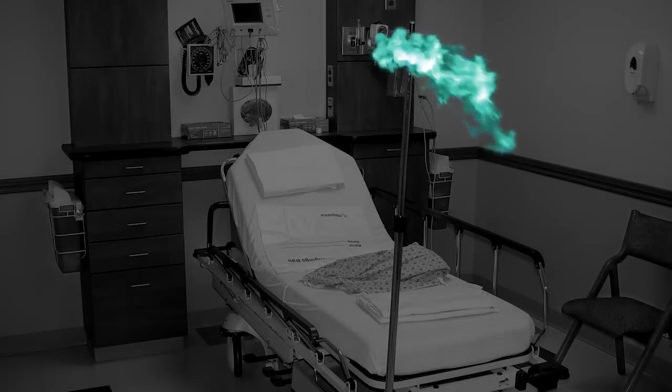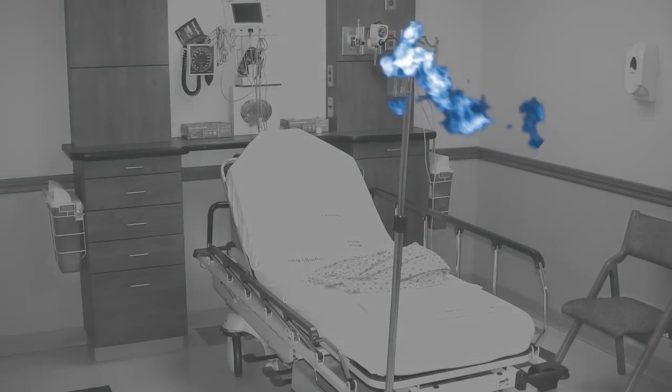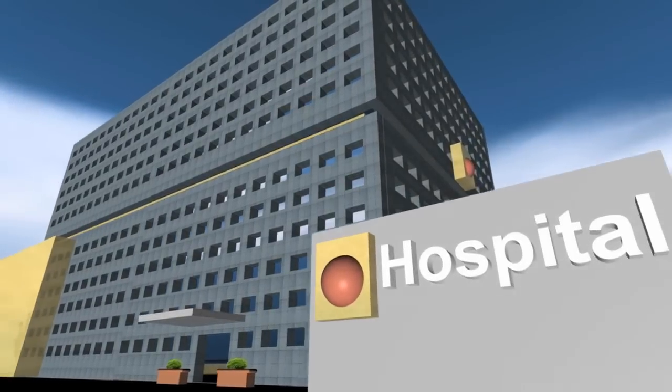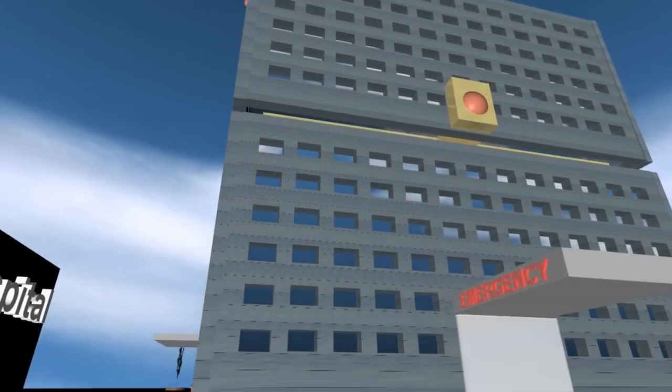costly and potentially dangerous medical gases could leak into patient rooms, possibly creating a highly flammable, asphyxiating, or anesthetizing environment. It becomes clear the ability to maintain an outlet live without shutting the system down becomes paramount.